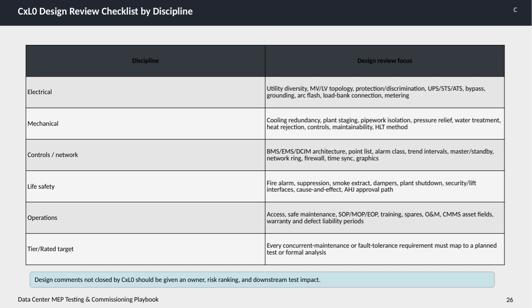as intended. When it comes to controls and network, the review looks at the building management system, energy management system, and data center infrastructure management architecture. This includes validating point lists, alarm classifications, trend intervals, master and standby configurations, network ring topologies, firewall setups, time synchronization, and graphical interfaces to guarantee robust and secure monitoring and control.